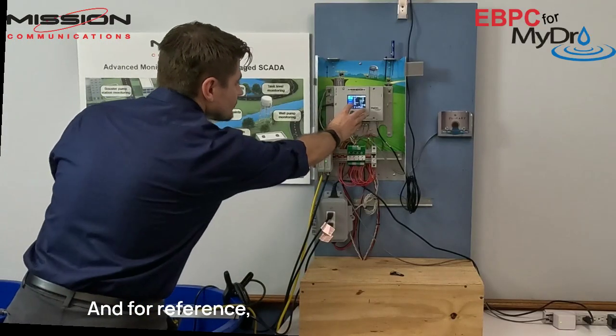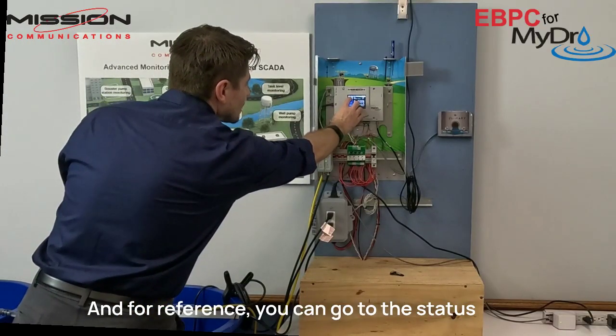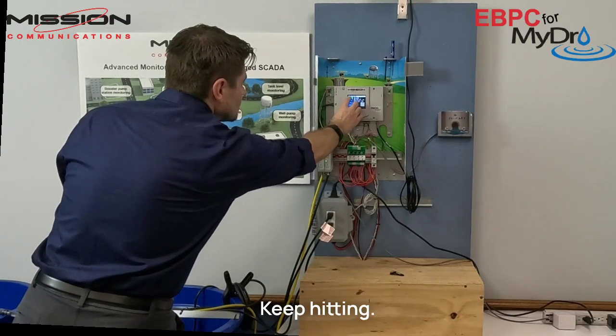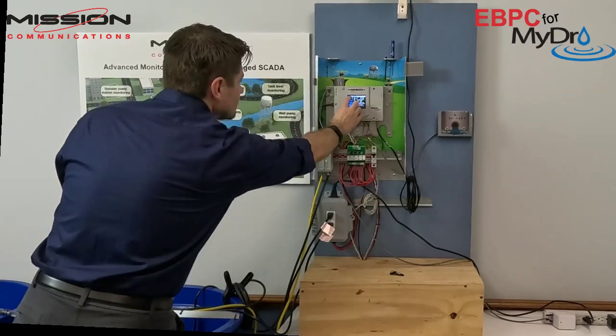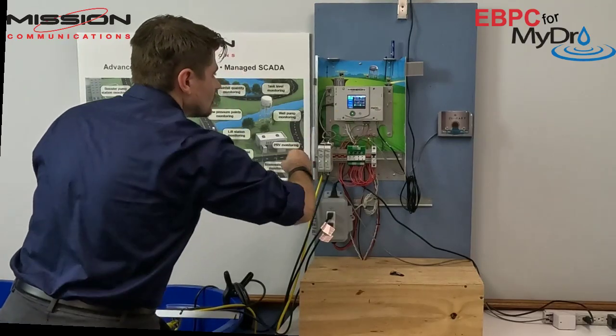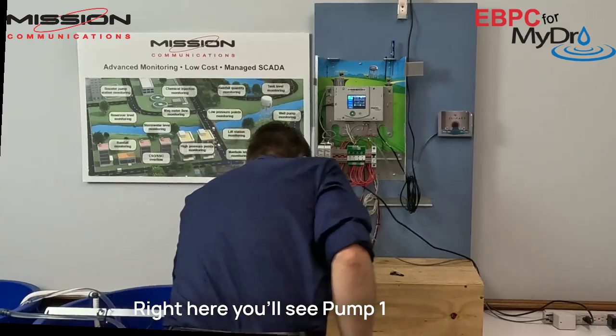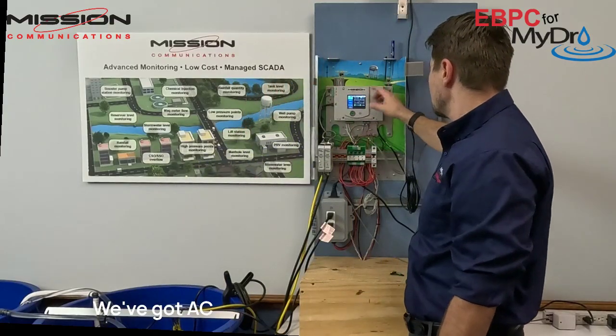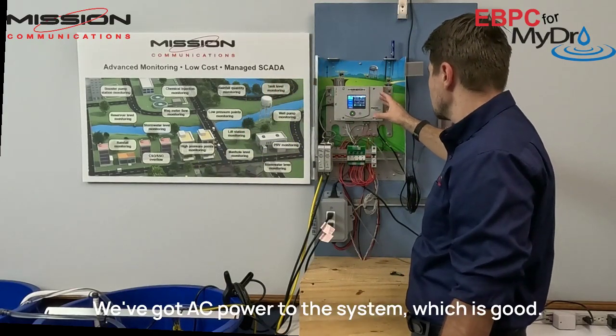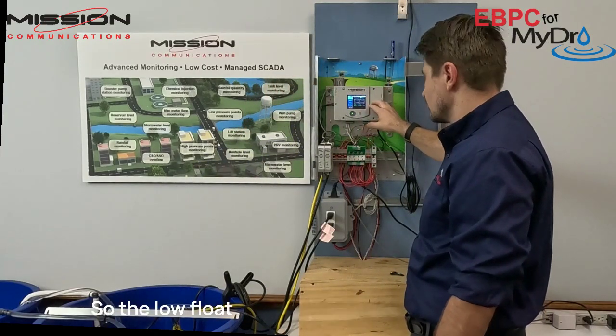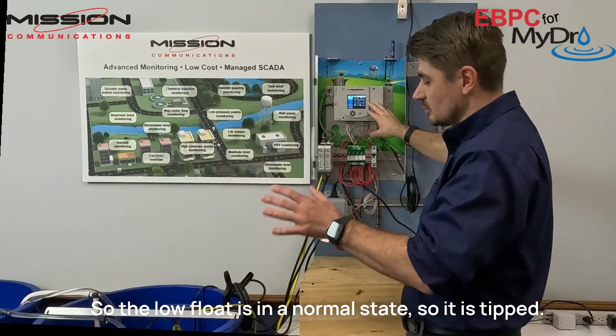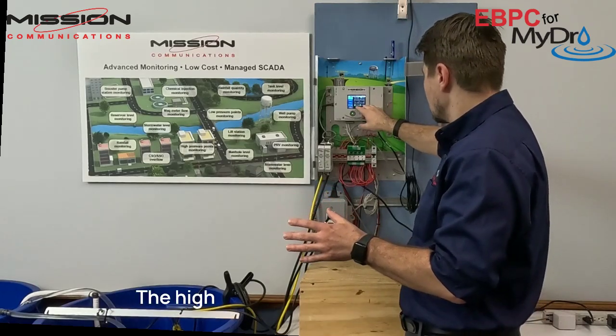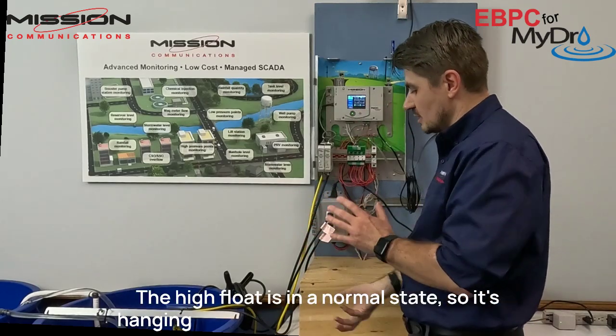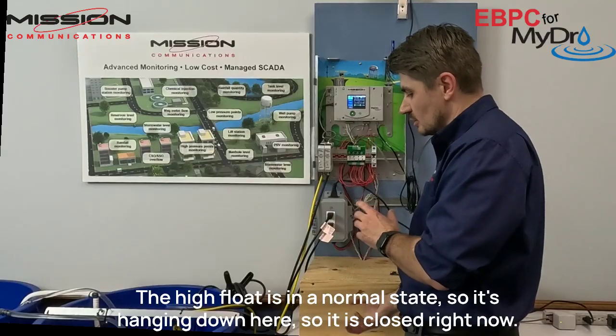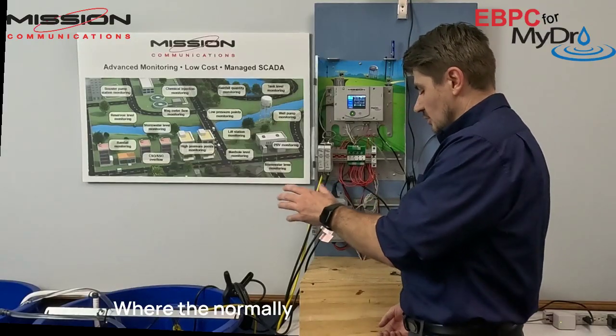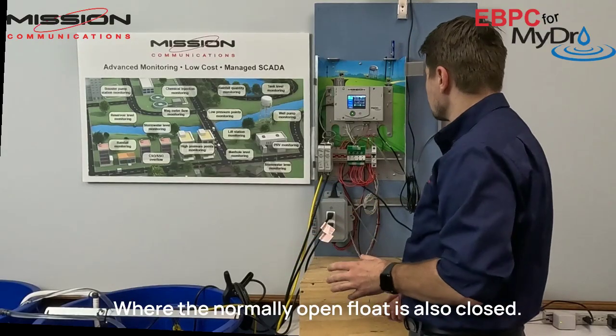And for reference, you can go to the status screen. Keep hitting. Right here, you'll see pump 1 and pump 2. We've got AC power to the system, which is good. So the low float is in a normal state, so it is tipped. The high float is in a normal state, so it's hanging down here, so it is closed right now, where the normally open float is also closed.